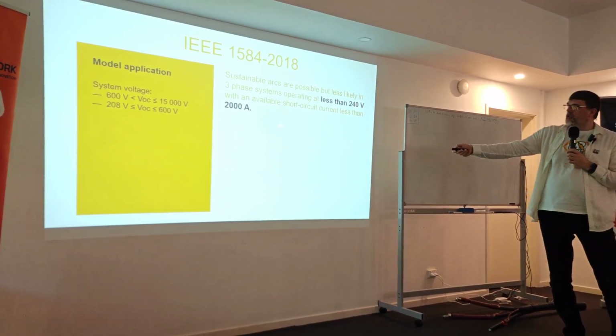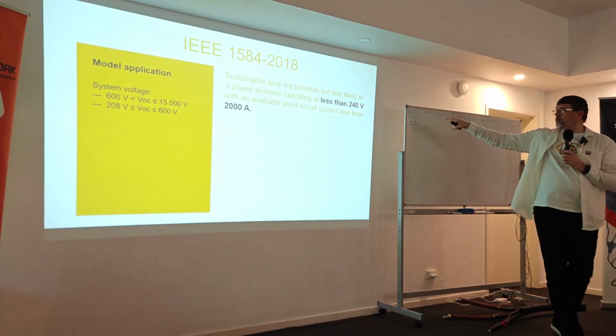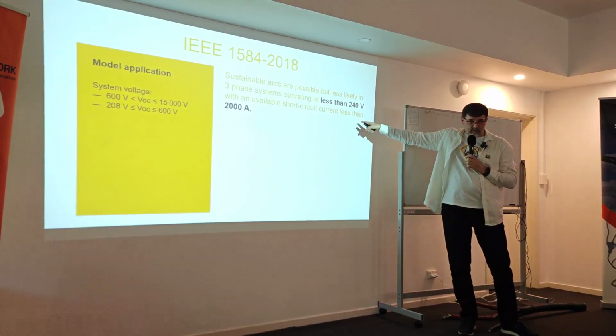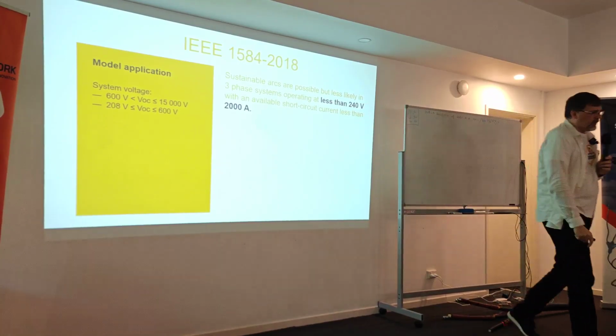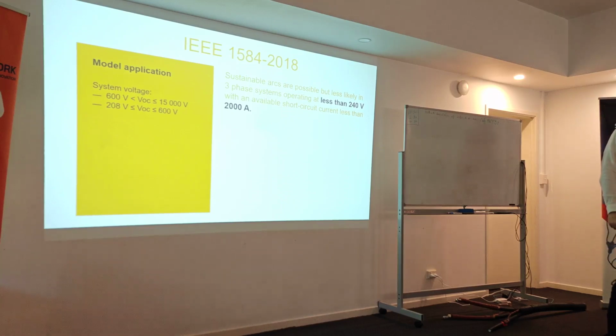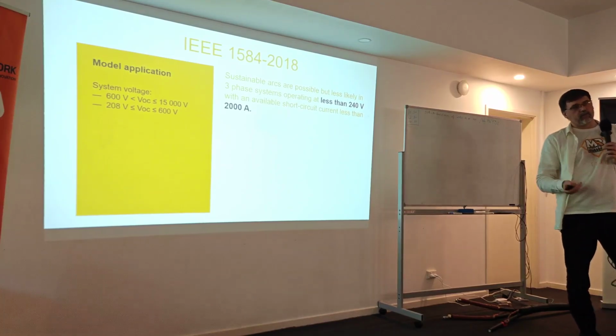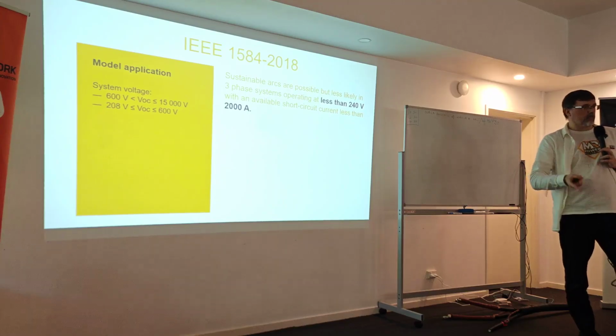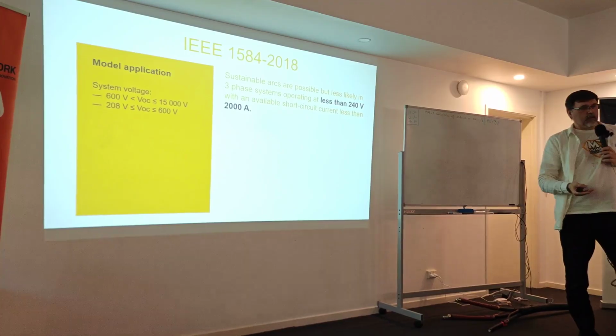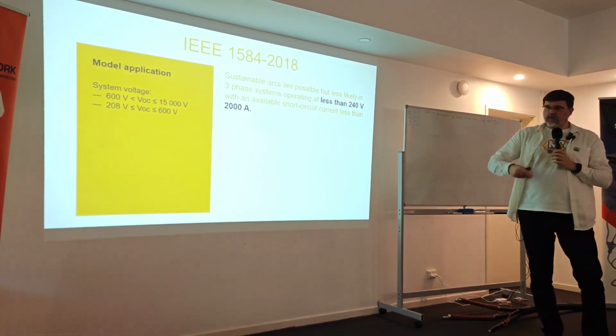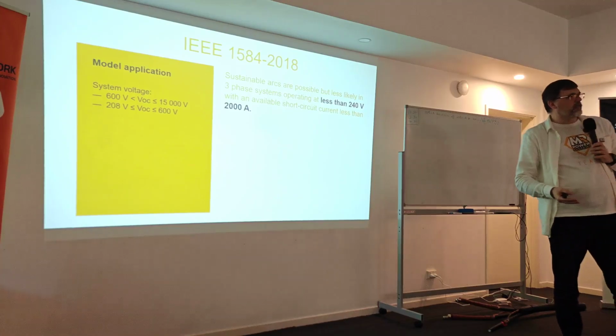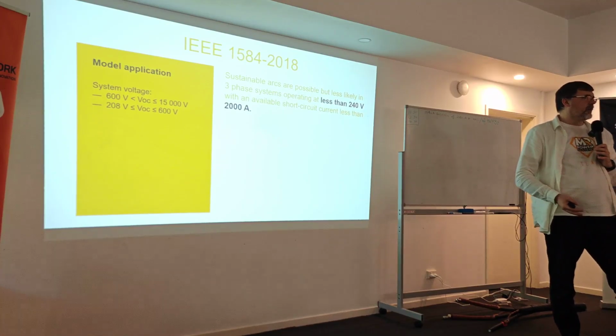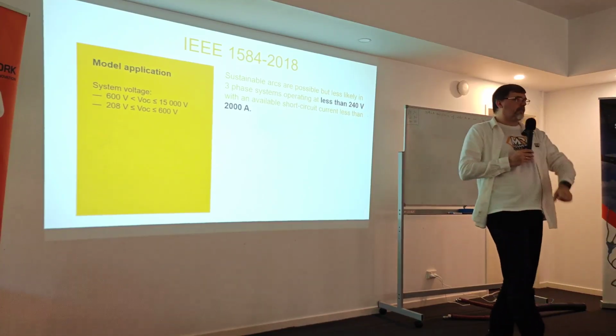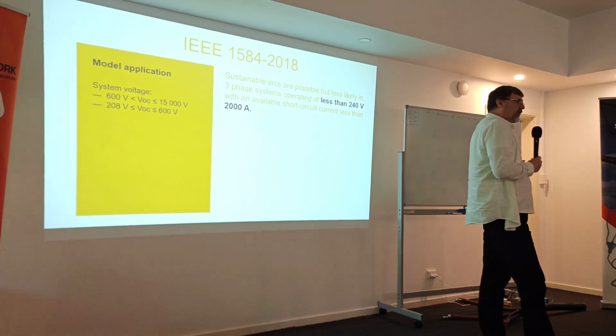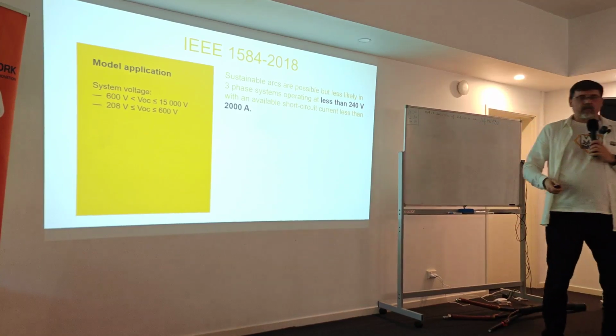Normally there is a note in the IEEE that says that below 240 volts, which is interesting, not 240 they wrote, and below 2000 amp, as tested, it's unlikely to sustain the arc. Sustain arc means that you can create the arc, but the arc will disappear because the distance, the energy and the voltage of the network are too low. It's still possible, but it's generally low. So it's hard to create, and when it just disappears by itself, it will not sustain and will not last for a long time, which means the energy is lower. If I just take the plug out, you will see the arc spark or something, but nothing is happening to me. That's because it's also disappearing very fast.